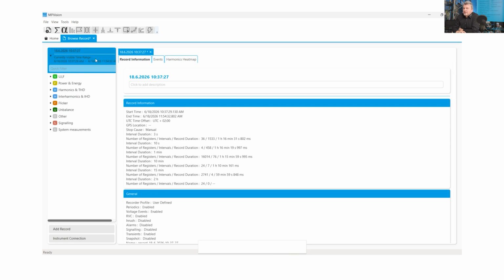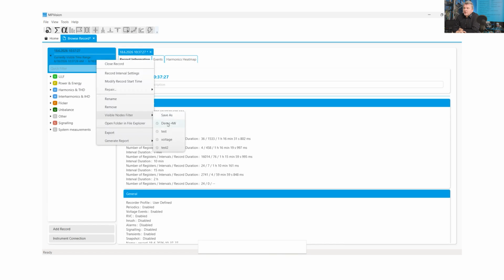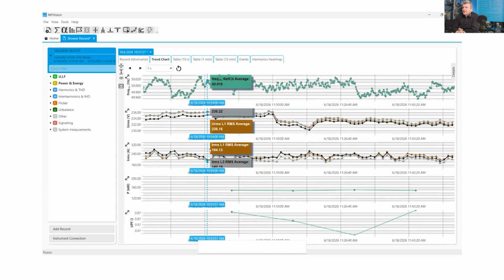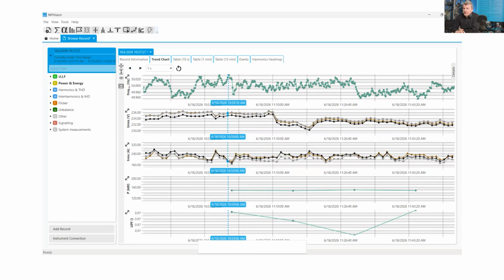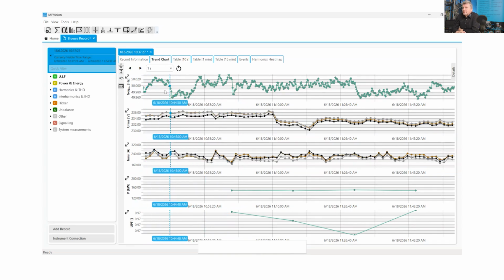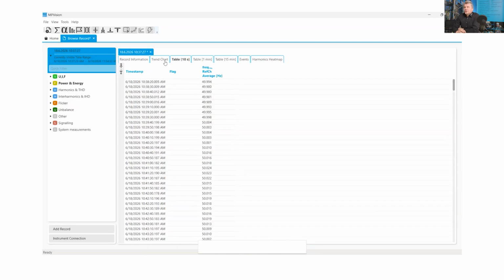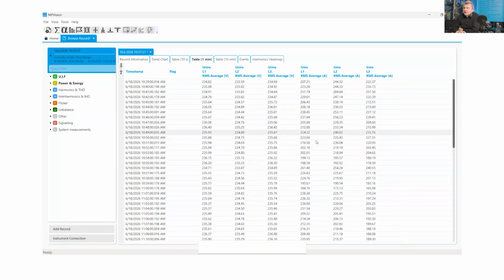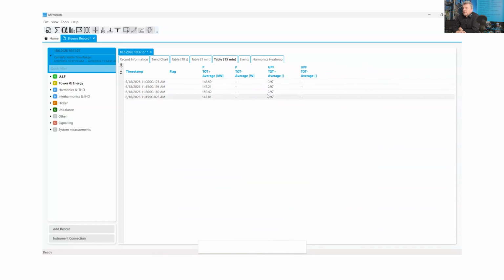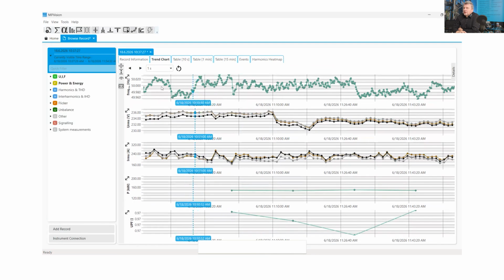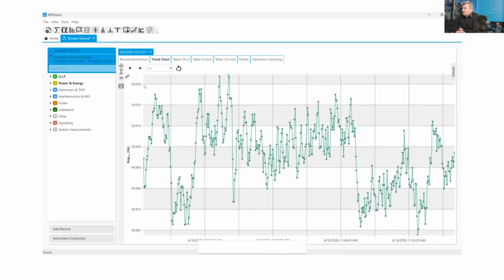We prepared some specific visible nodes. Here is an example of one demo view where the registers are automatically pre-selected, defined by the user. So you can specify your own approach to what you want to see. For example, in the table with 10 seconds we present the frequency value, which is measured according to the standard interval. Then you have 1 minute, which is the general recording period, voltage and current, and 15, which is for demand. With the trend chart, you can extend a specific trend and place different markers.